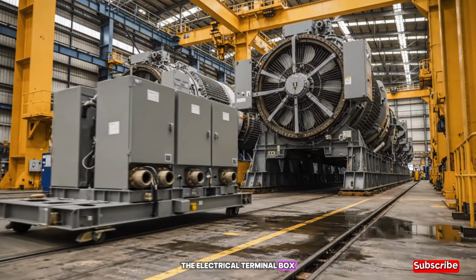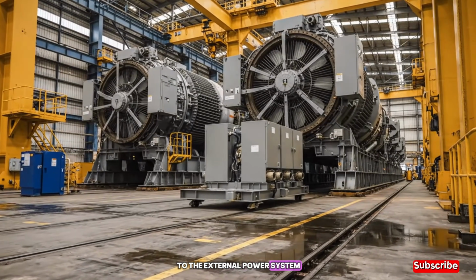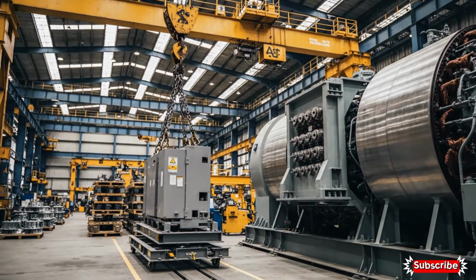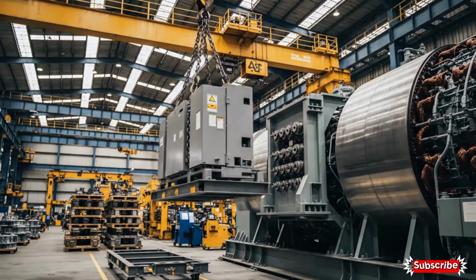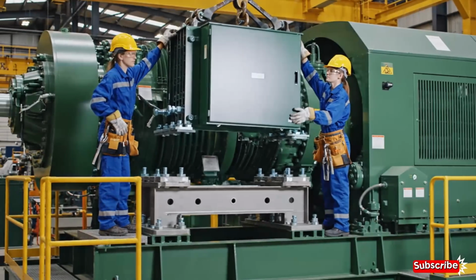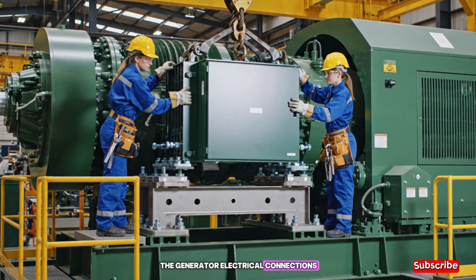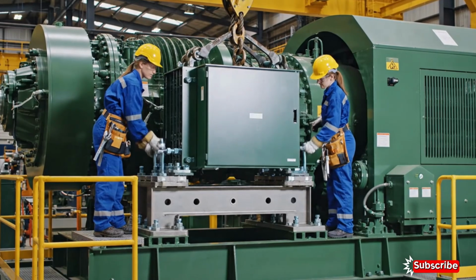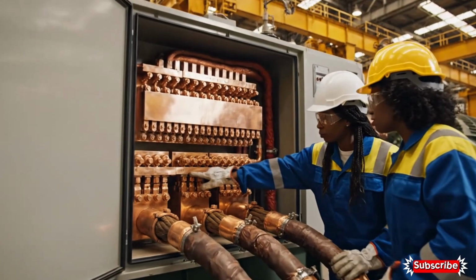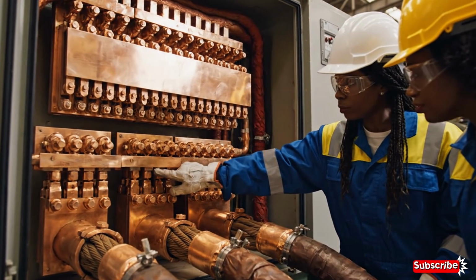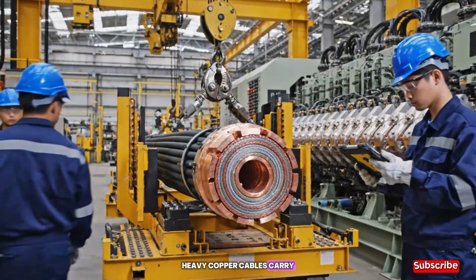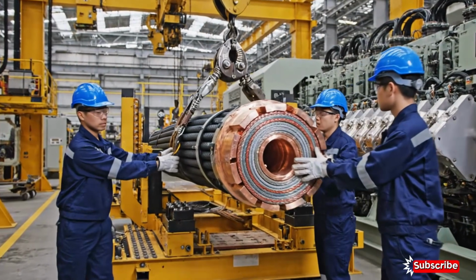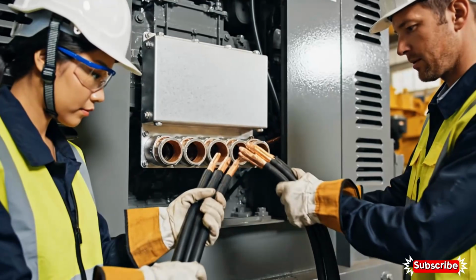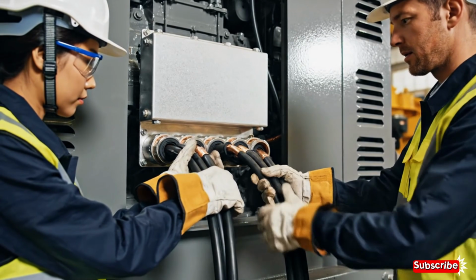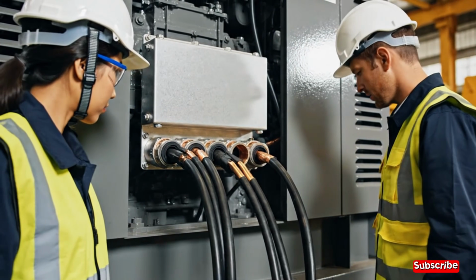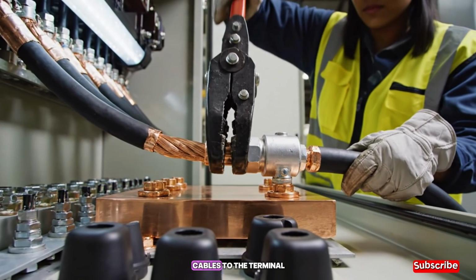The electrical terminal box connects the generator windings to the external power system. The terminal box houses the generator electrical connections. Heavy copper cables carry electrical power from the generator. Compression connectors secure the generator power cables to the terminal bus bars.